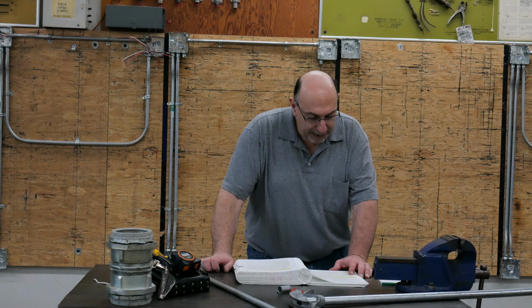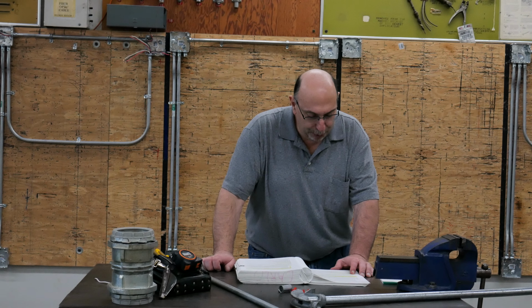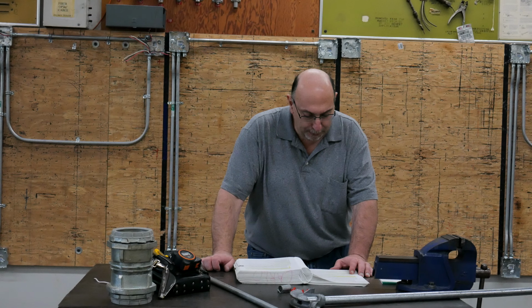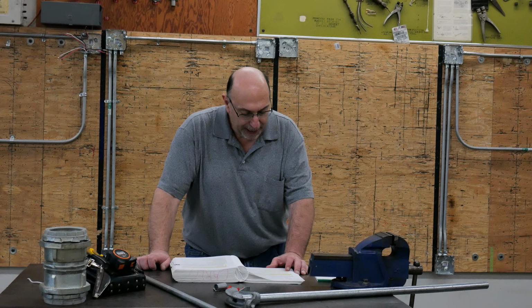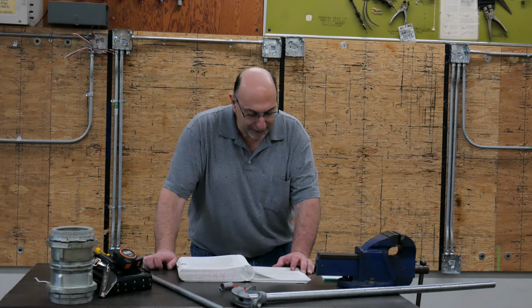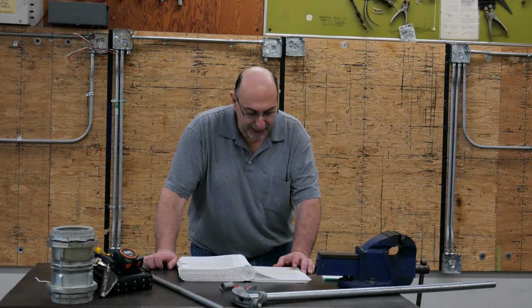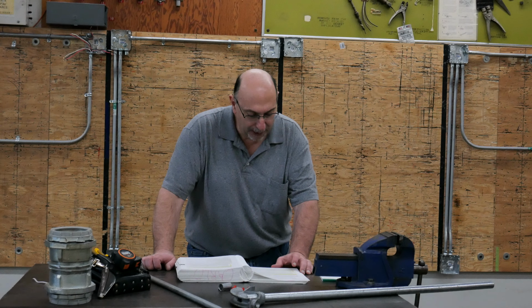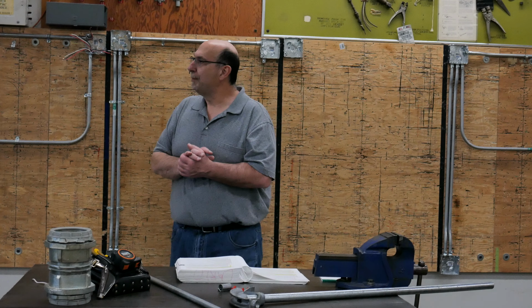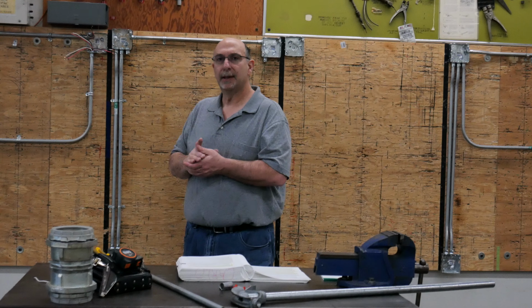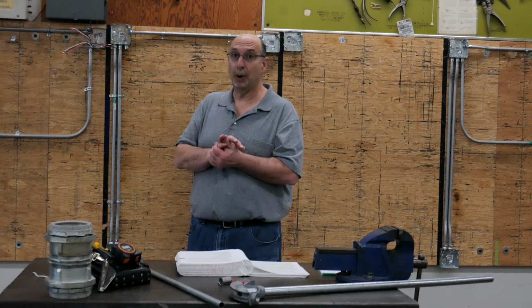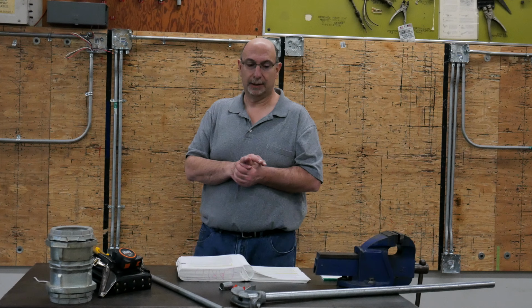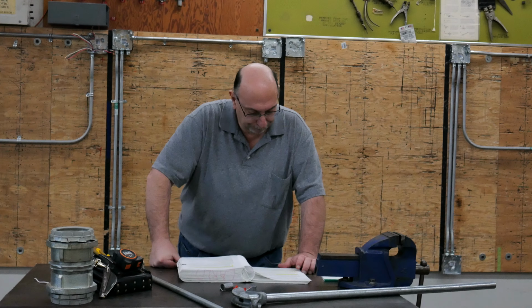Subrule A, an insulated type bushing unless the equipment is equipped with a hub having a smoothly rounded throat. Subrule B, insulated material fastened securely in place that will separate the insulated conductor from the raceway fitting. So I know in some cases, if you're running armored cable or flex, the fitting that you actually purchase will actually have a smooth rounded throat. That will suffice in accordance with Subrule A.